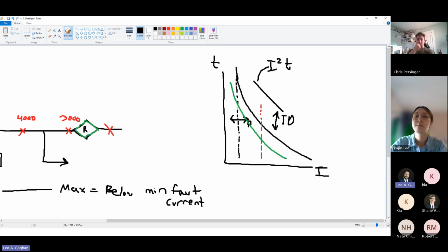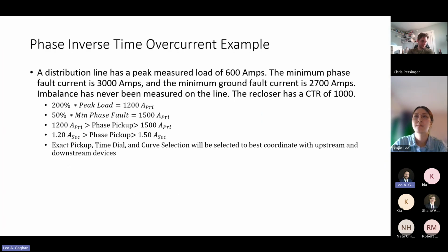And I think one of the toughest parts that people struggle with in protection is that oftentimes there is no perfect answer. In math, 2 + 2 = 4, always. No debating it. The right answer in protection is not always a perfect answer. There's usually a number of things that are acceptable. You need to work within what's acceptable, but then within that, you do have some discretion as far as what you select. People struggle with that sometimes. Why did you pick 1.3 versus 1.4? They were both acceptable. Yeah, but I like to, usually comes into play.